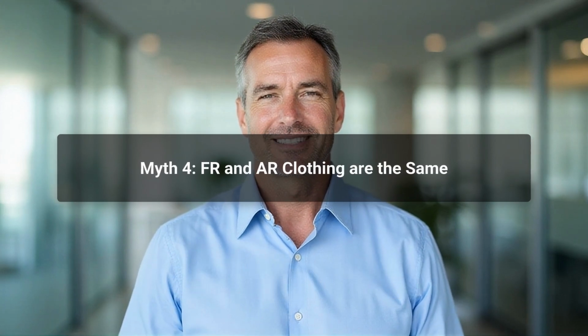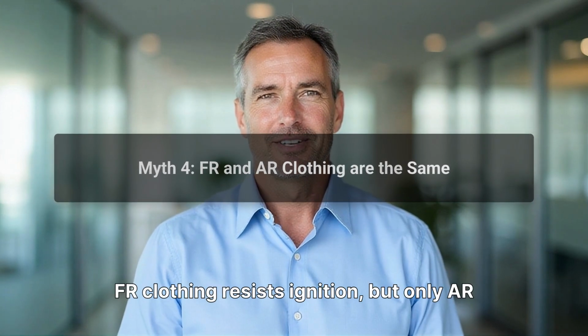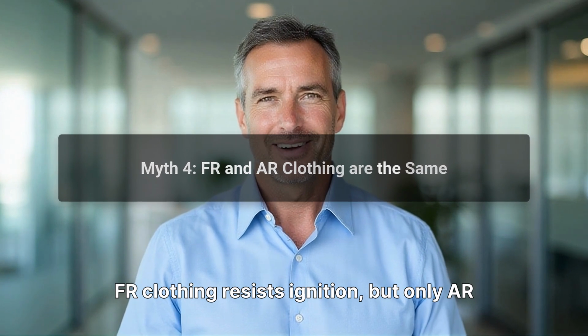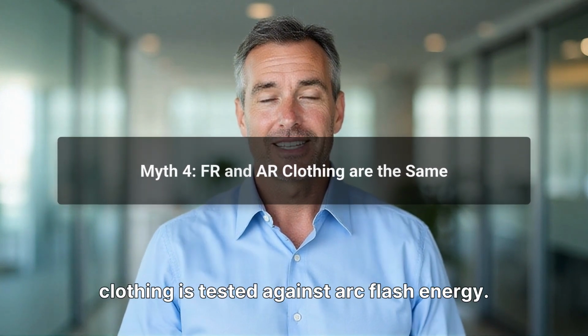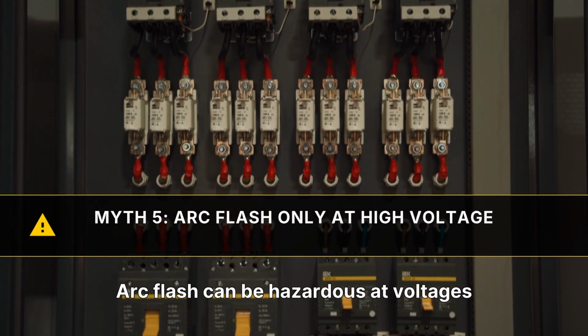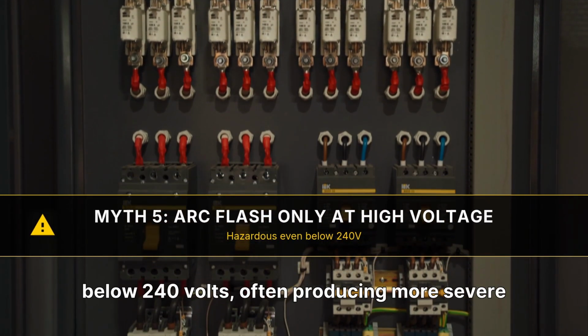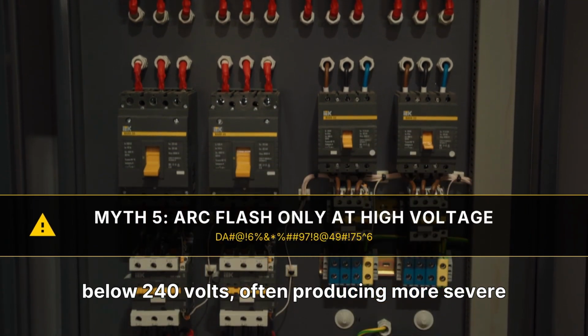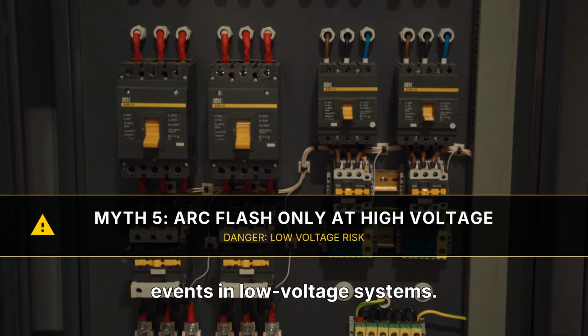Myth 4. Flame-resistant and arc-rated clothing are the same. They are not. FR clothing resists ignition, but only AR clothing is tested against arc flash energy. Myth 5. Arc flash only happens at high voltage. Arc flash can be hazardous at voltages below 240 volts, often producing more severe events in low voltage systems.